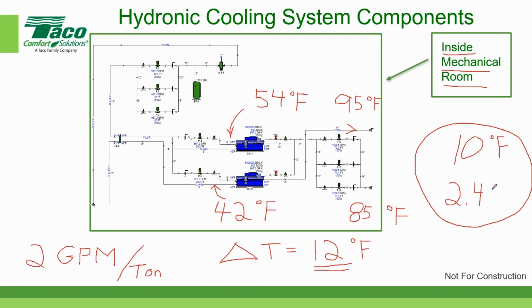Well, here's another comment. What's your statement about this statement here? The cooler you run the towers, the more efficient the chillers will operate. 95 is the upper limit. Yeah, that's absolutely correct. But generally, you're restricted by nature, meaning the weather. So if you happen to be in New England, we'll just use New England as our starting point here.